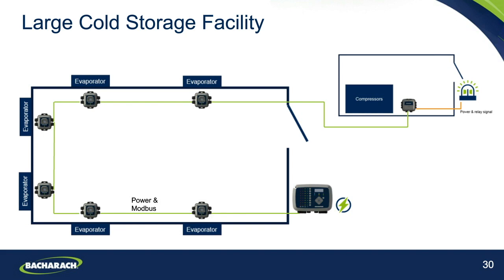Okay. Well, ammonia is lighter than air. So in the event of an ammonia leak, we would typically expect to see the gas rise to the ceiling in the space and do so fairly quickly. One of the key things to look at within any application, whether we're talking about ammonia or other gases, is what the airflow is. So although we would expect to see gas accumulate close to the ceiling, in terms of where those detection points are in relation to where the leak is most likely to come from, we would want to look at that placement with regard to what the airflow within the room is as well.